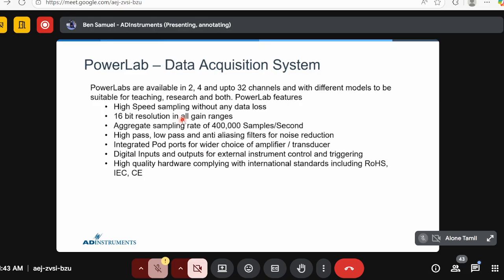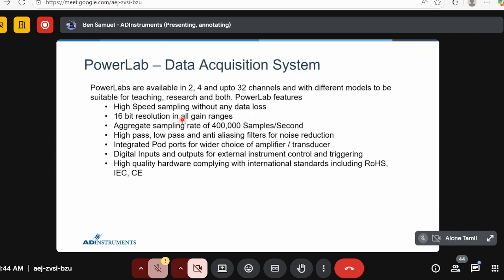It is because biomedical signals are very, very low in amplitude and noisy, and it will often require extraction of fine details. That's why we use a 16-bit ADC. Some examples of biological signals: the ECG, whose amplitude will be around 0.5 to 5 millivolt. EEG is even lower, 10 to 100 microvolt. EMG, the electromyogram, from muscle activity, is around 5 millivolt.